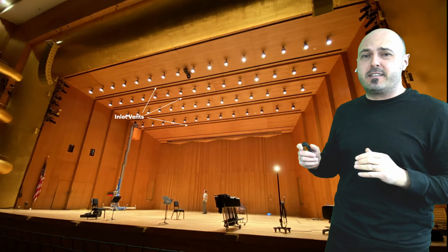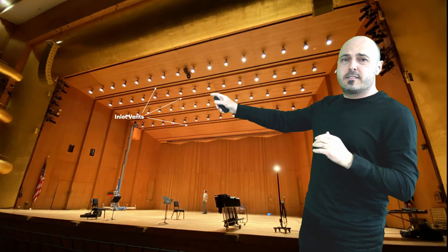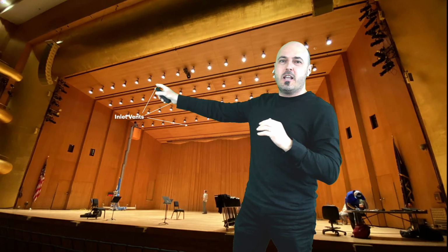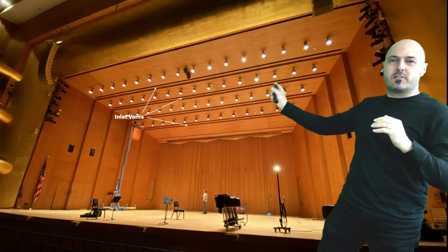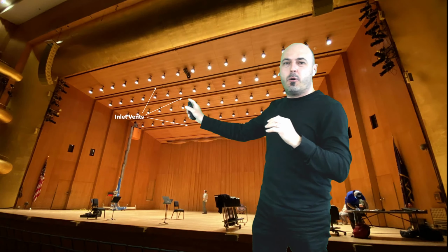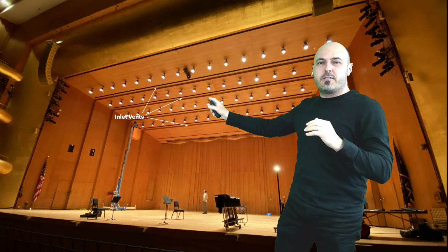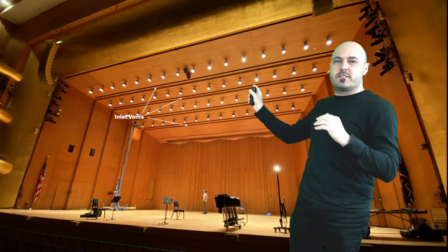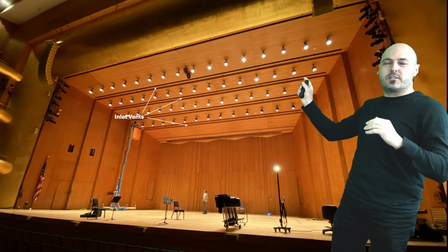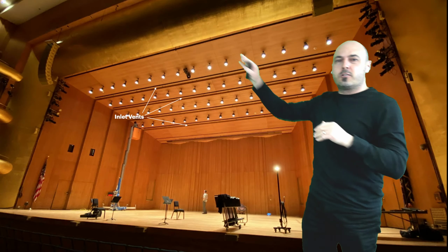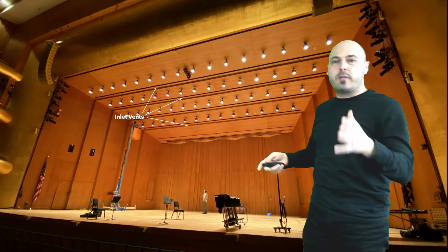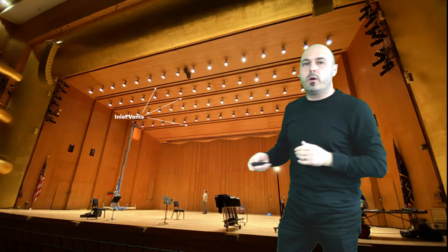Now I want to orient you a little bit about what's going on. There are inlet vents at the ceiling up above, as you can see here, if I can put my finger just on it. All of those horizontal lines are inlet vents. Now, it's not completely inlet. There's an inlet, and then there's a gap, then there's an inlet, and then there's a gap. I'll show you a picture from behind it. So those were the inlet vents. We clearly needed to capture those vents. What's also important is that there is a door over here and a door over there. Those turned out to be very critical in our mitigation strategy, so I want you to remember those.